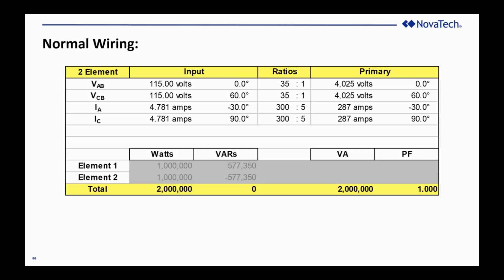Now let's flip the polarity by 180 degrees of one of the phases. So I flipped from minus 30 degrees on the A-phase current to 150 degrees on the A-phase current. And what happened is my total watts went from 2 megawatts to 0. My total megavars went from 0 to a number that is approximately equal to the VA in the opposite direction. And those are my two indicators that I've got a problem and what the problem is.